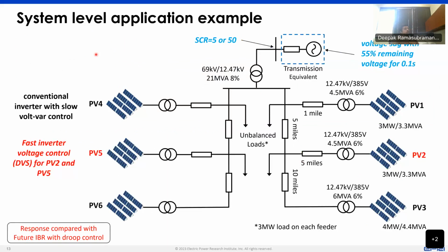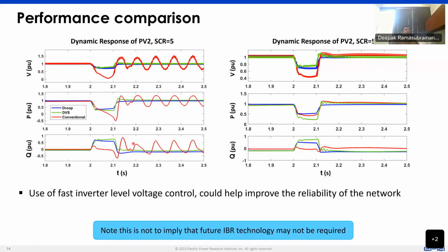We can consider the same example on a distribution network. So if you have a network that is connected to the transmission system through some equivalent, and you have a bunch of feeder elements and a bunch of PV plants, then compare the response between having this inverter level voltage control on these two PV plants and some form of future inverter control that is also black start capable. So the red curve is the conventional IBR that doesn't have this fast voltage control at the inverter level. The green curve is the enhanced IBR, which has this fast voltage control at the inverter level. The blue curve is the future IBR that can provide even black start capability. In this particular scenario, we are not looking at black start capability, but rather at any system running, for strong systems versus weak systems.